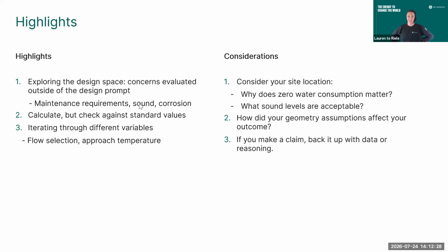One more example that I'll give, that I gave to the live group, is on cost. I saw some operation costs that were $2 million a year. Considering the size of the plant, when you get to that outcome, we know that the purpose of this plant is to produce power and to make money, right? So one check that I didn't see anyone do that I would have loved to see is to say, okay, we know based on public data the power output in kilowatts or megawatts from this plant. How does my power consumption stack up against that?